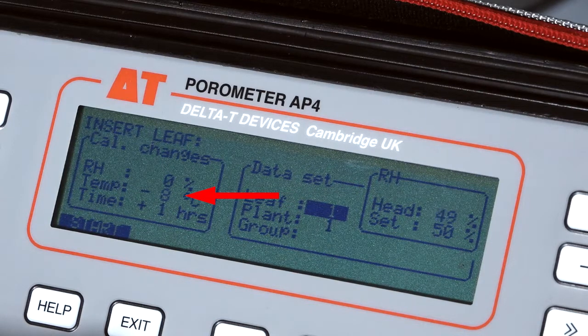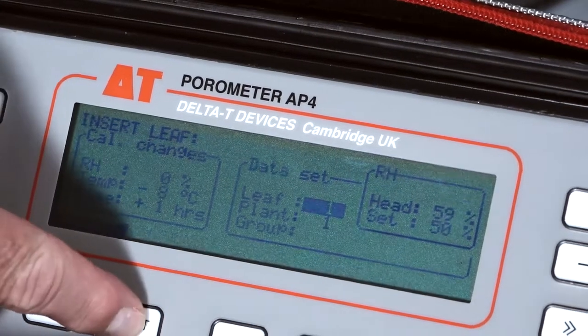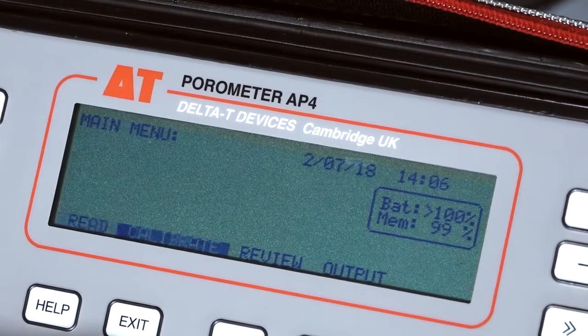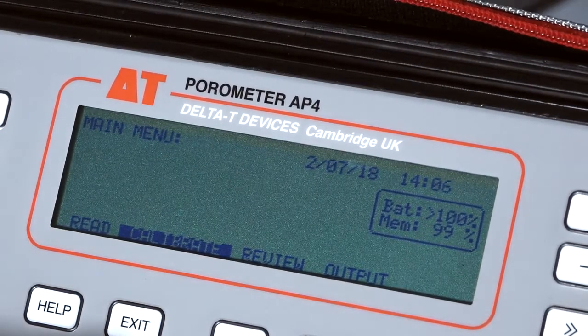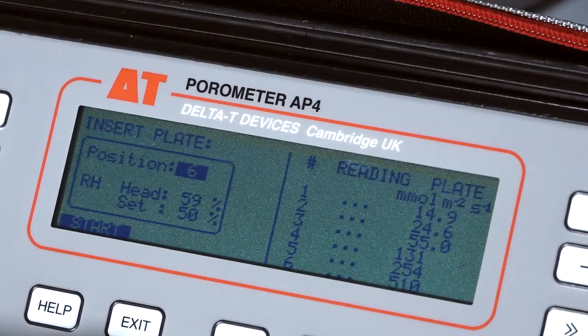And this is a prompt for you to think about recalibrating, because humidity and temperature changes throughout the day, and especially day to day. So if, when you try to take a reading, any of these values are flashing on the screen, then you really should calibrate the system. And that's what we'll do next.